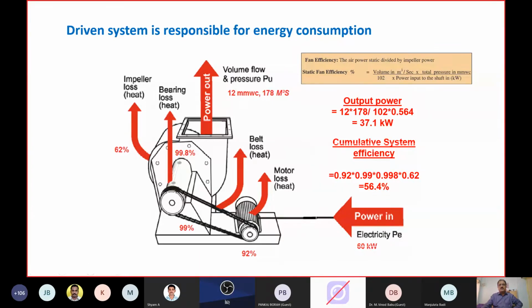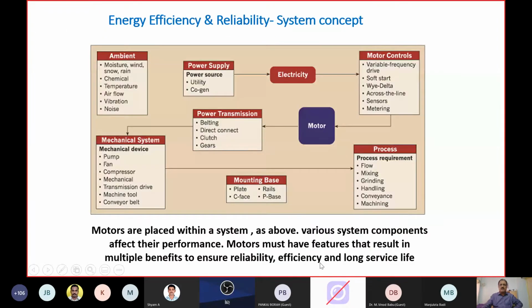It is possible to get a single-digit saving from these three elements, that is motors, belts, and bearings. A two-digit energy saving opportunity is available through impeller replacement or total system replacement, such that the efficiency can go up to as high as 75%. So a two-digit saving in the system is possible if you address the total system as a whole, not just the motor. Again, we saw this slide in a previous form.